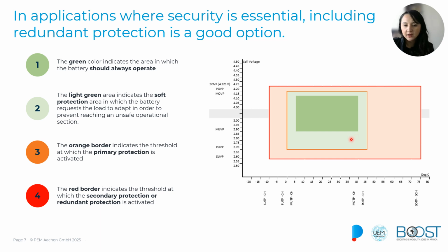Then we have the orange border that we can see over here, and this is the primary protection condition. When the battery voltage, temperature or current crosses this border, the BMS takes corrective actions to prevent failures, and usually this is done by disconnecting the battery and isolating it from the system. And then we include a second border that is the red one, and this is the redundant protection. These are basically backup protections that will act in case the primary protection system fails, or in case that system is bypassed.